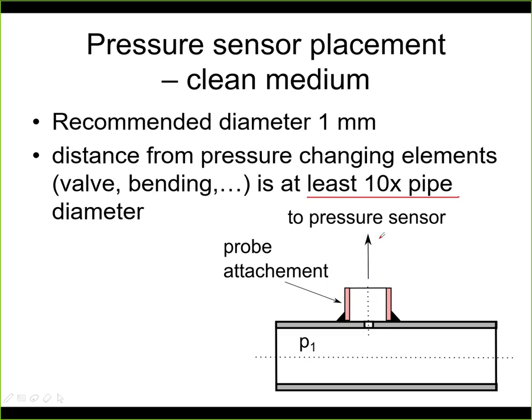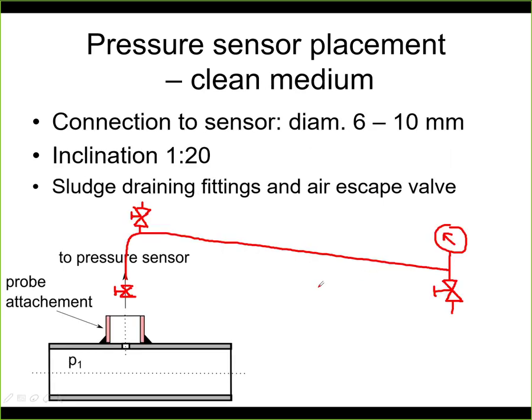Then this goes to the pressure sensor itself. But this pressure sensor is not connected directly to this opening, but we use some valves to allow the connection and disconnection of the instrument. So typically it looks like this. Here is the probe where we have the sensor attached. Then we have some piping that goes to the pressure gauge. So this is my pressure gauge. And typically this connection is made with a pipe of a diameter between 6 and 10 millimeters. Now you can install anywhere you like this instrument, but you need to keep the following rules.